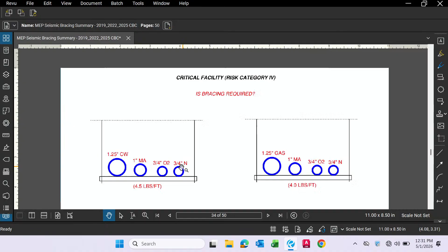Okay, all right, last one on this. This one right here. Risk category 4 building. The annex is killing you. But yes, it requires bracing because the cold water is over it. Cold water is greater than category 3. This is category 4, right? Yeah, so it's over 1. That's correct. It gets an importance factor of 1.5, and because of that, it needs to be braced. Right? See how many more do we have? We have 3 more, 2 more, right?